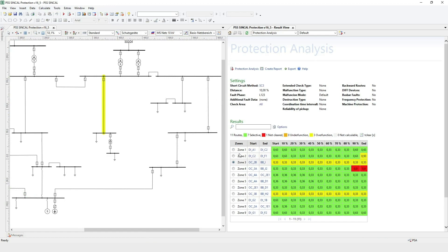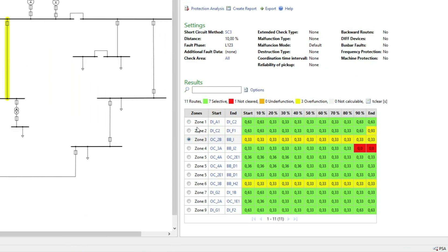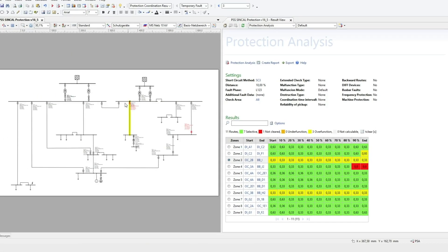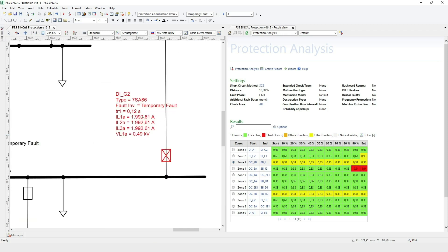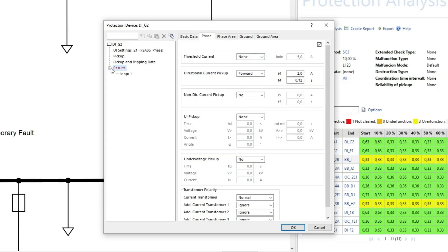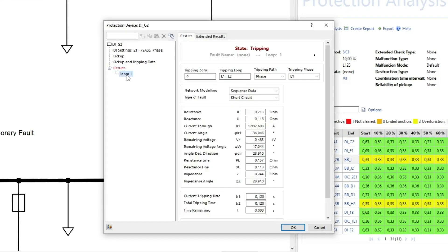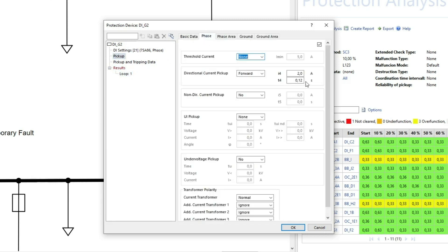To take a closer look at the weak points, we'll use the protection simulation. Simply right-click a cell and select Calculate. Here we see that device DIG2 doesn't trip correctly because it isn't the main protection for the yellow highlighted protection area, and this protection device will trip after 0.12 seconds. To see which zone tripped, double-click the device and select the results entry. In the settings of distance protection device DIG2, we can see that the 4i zone, also known as the directional end time, was tripped. The directional end time is usually used as a backup, so the time setting is usually quite high. In this case, a simple fault occurred during parameterization — the setting must be 1.2 seconds and not 0.12.